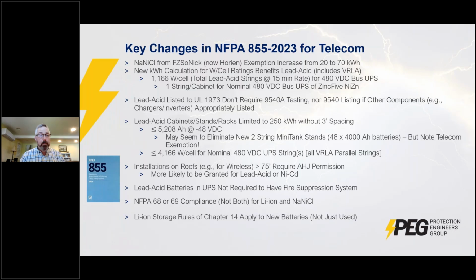So based on that data brought to the committee, they said, yes, this sodium nickel chloride is a safer technology than originally thought. So they increased the threshold quantity of when the standard applies from 20 to 70 kilowatt hours for that chemistry. Similarly, I mentioned 70 kilowatt hours for lead acid batteries. That's the threshold. That's really based on long-term discharges as we use for telecom, maybe some other utility applications for peak shaving and so forth.